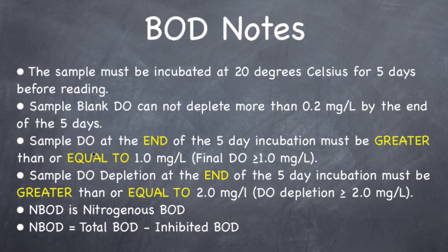For your actual samples, at the end of the 5-day incubation the final DO must be greater than or equal to 1 mg per liter. So you've incubated it for 5 days, you pull it out, you read the DO — if it is less than 1 mg per liter, you cannot use that sample. You can use other samples if they do meet this rule, but this sample is invalid. Throw that sample out, you can't use it at all.